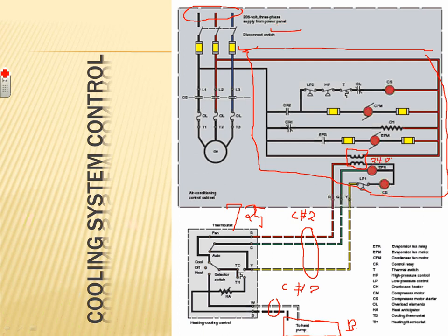Since this is outside, there's also a cabinet heater inside here, and a bunch of other things. It's a whole big unit. That's why on the nameplate, you're going to find something called rated load amps for the whole equipment, and they give you one big rated load amp, because I have heaters, I have pumps, I have a lot of control coils. It's not just a big fan motor. There's a whole lot of things inside this box that's called the AC unit, the condenser and the compressor.